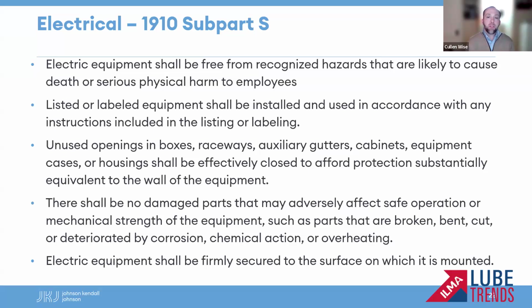There shall be no damaged parts that may adversely affect safe operation or mechanical strength of the equipment, such as parts that are broken, bent, cut, or deteriorated by corrosion, chemical action, or overheating. Again, a pretty broad one, but this spells out pretty clearly that if you have damaged equipment, it would fall into this category and it's something that could be cited. All right, and then electrical equipment shall be firmly secured to the surface on which it is mounted. So everything has to be securely affixed to a wall or permanent setting.